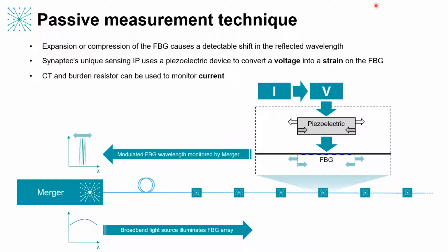And the speed at which we get the information on a measurement back from that point is literally the speed of light in fiber, which actually is about the same speed as a traveling wave in a conductor. So it's about 5 microseconds per kilometer is the delay. And that's a really interesting point, because that's how at Synaptec we can timestamp our measurements remotely without having GPS there, because we know precisely how long it takes the light to travel in analog form from our sensors, which could be 50 kilometers away, back to our interrogator.